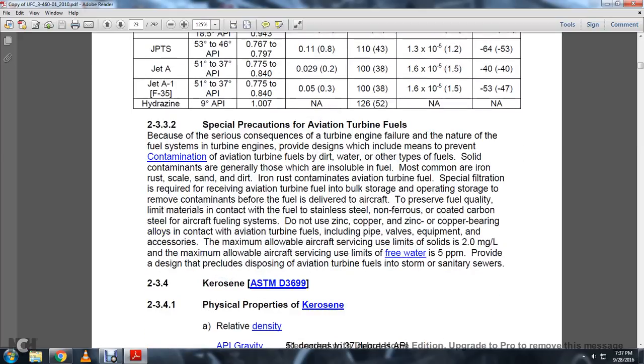2.3.3.2 Special Precautions of Aviation Turbine Fuels. Because of the serious consequences of turbine engine failure, the nature of the fuel system of the turbine engines provided with the design would include means to prevent contamination of aviation turbine fuel by dirt, water, and other fuels. Solid contaminants are generally those which are insoluble in fuel. Most common are iron rust, scale, sand, and dirt.